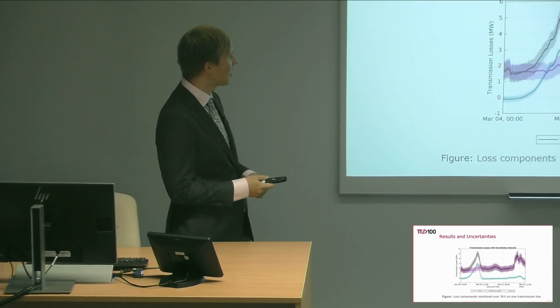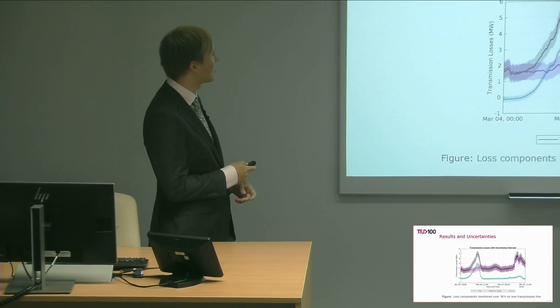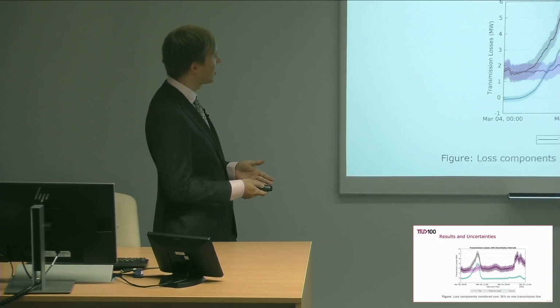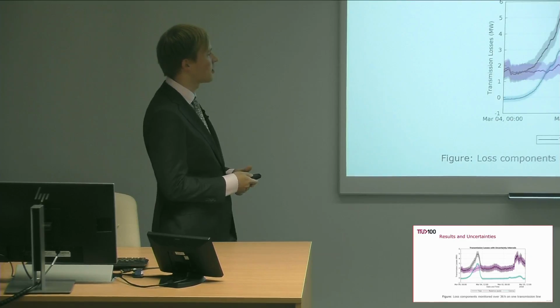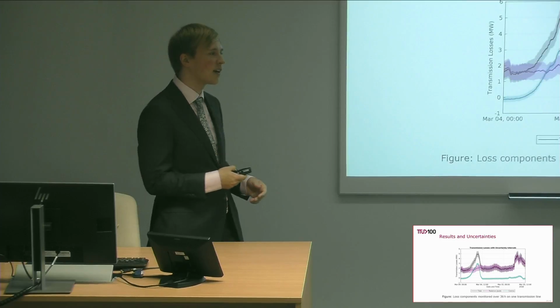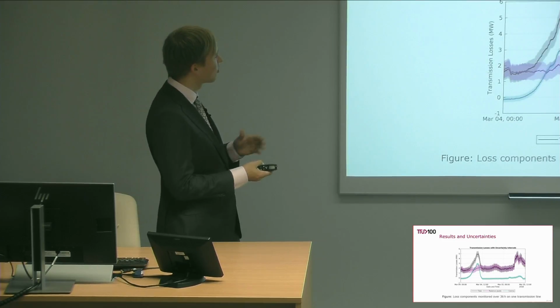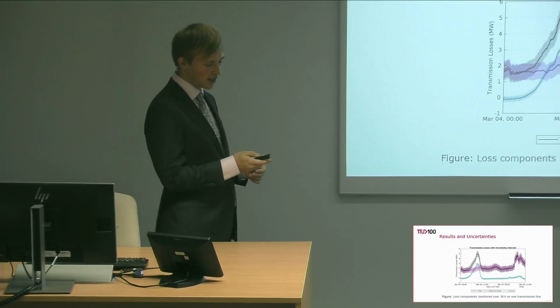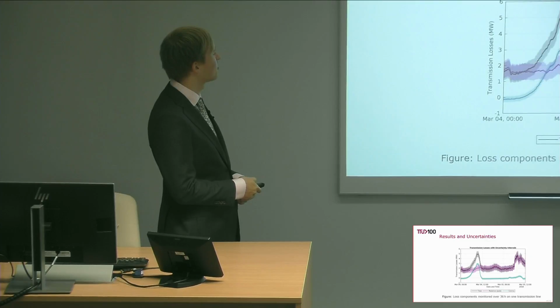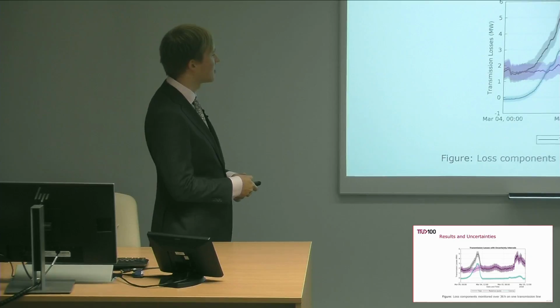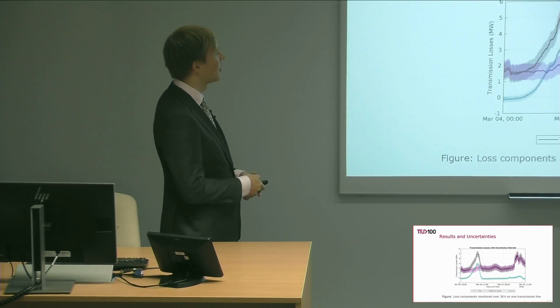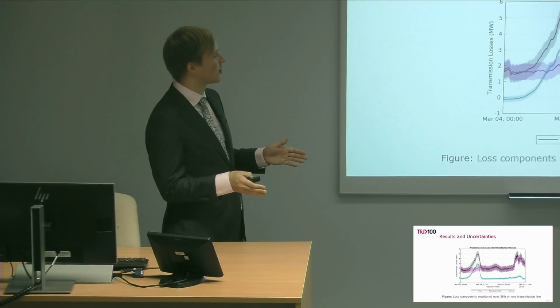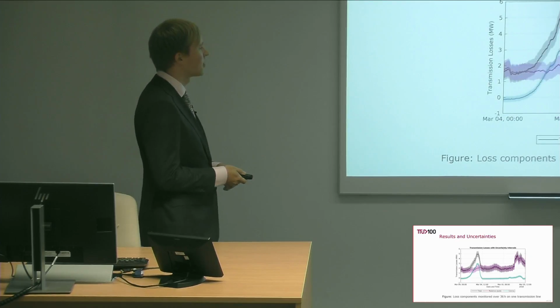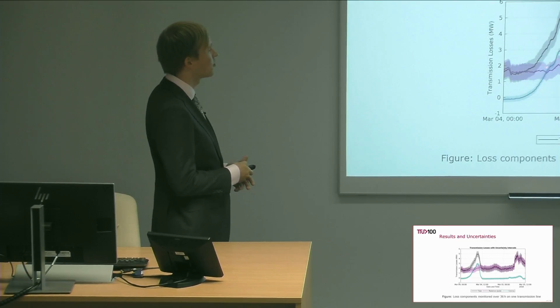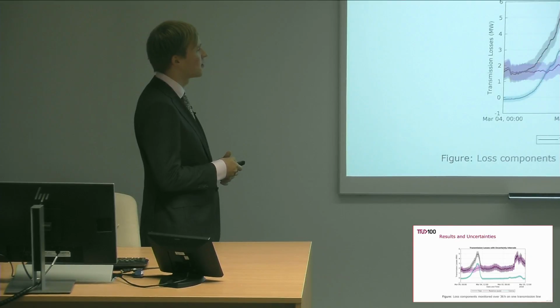In some cases, what is done is that the total losses are measured, and then the joule losses are approximated based on measured current and a known resistance, and corona losses are evaluated as the difference. But we can also see that we obtain a significantly smaller uncertainty interval if we measure corona losses as a separate component from synchronized phasors measured from both ends, because with the other approach we have to consider these large uncertainty intervals.